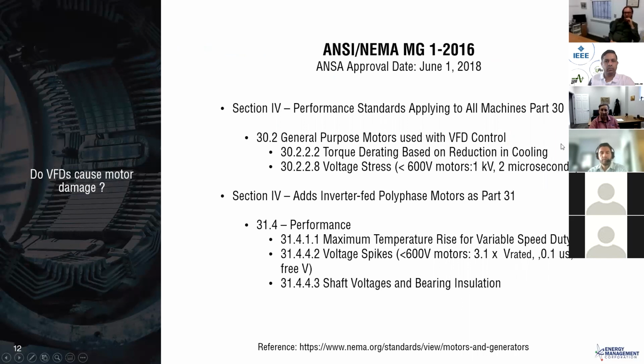And we think of NEMA MG1 as Part 30 and Part 31. Part 30 is typical general purpose machines that could be used with VFD control. And Part 31 deals more with actual inverter fed motors. There's no term inverter duty motors in the NEMA MG1, so inverter duty is kind of an industry term that is trying to address this. When you think about the term inverter duty, it could mean a lot of different things to a lot of different people.